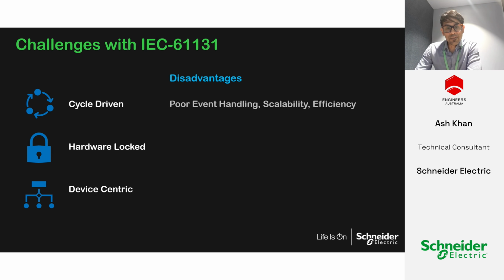So what are the disadvantages of cycle-driven? It's poor event handling, because it has to run through the whole logic before it comes back to the IO cycle again. Scalability becomes a challenge too - if you add any further logic to your existing PLC logic, the timing and code have to be revalidated. It's not efficient in reutilizing resources because it carries all those IOs across, reading thousands of IOs, revalidating the logic, then turning something on or off. Even if nothing's changing, it's continuously running the cycle.